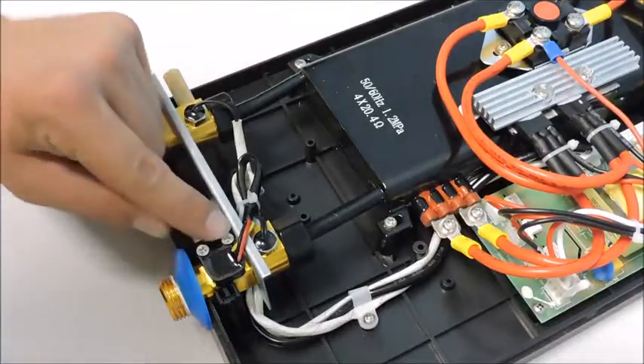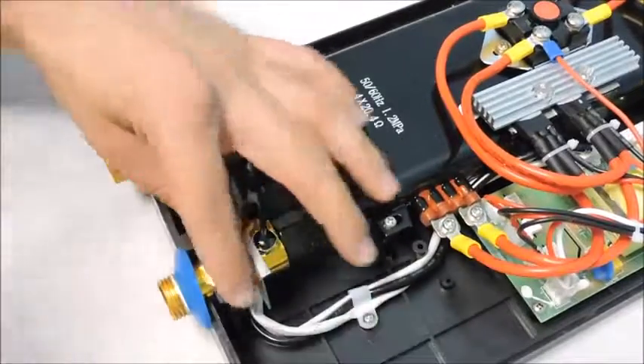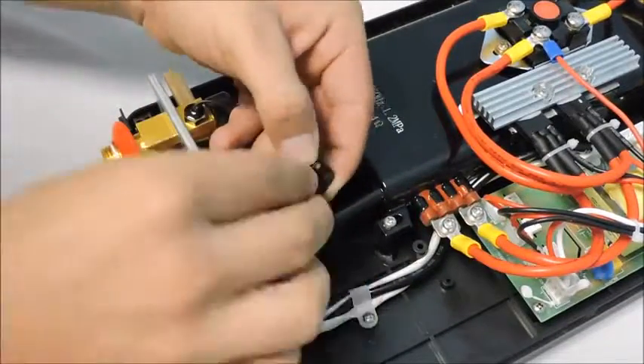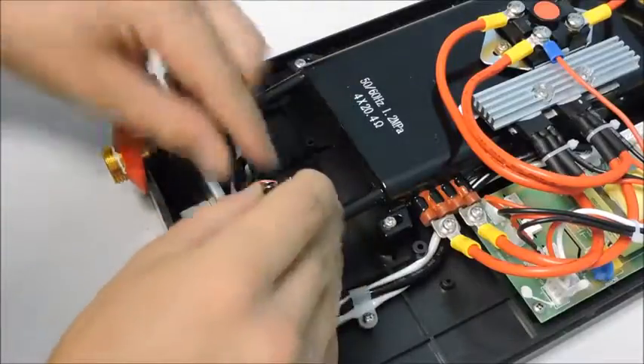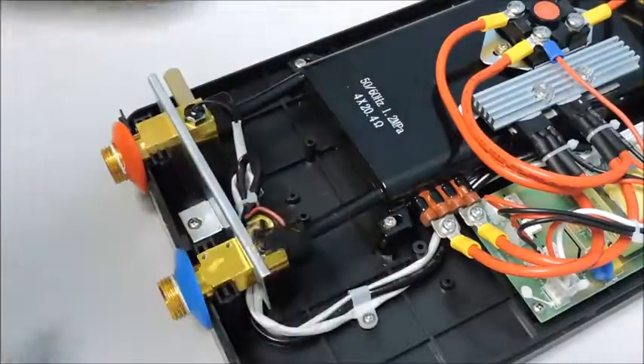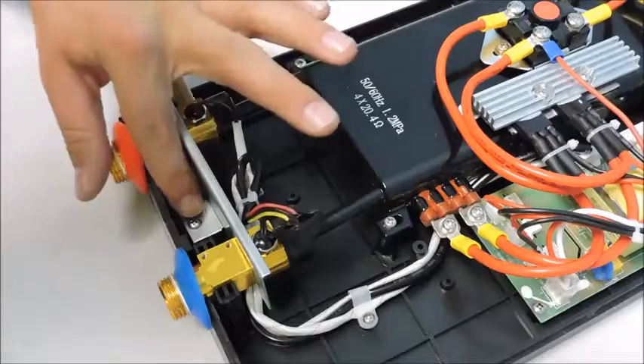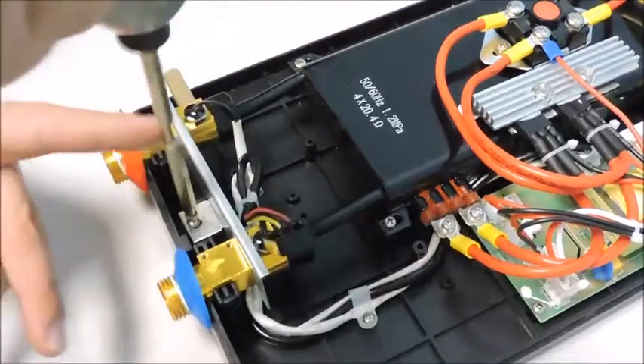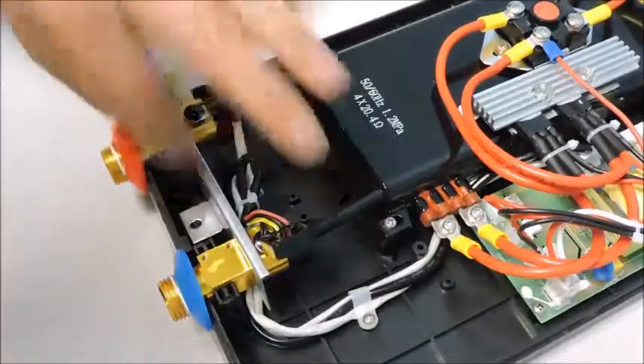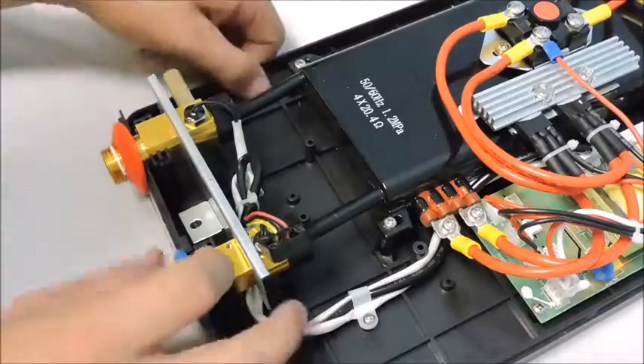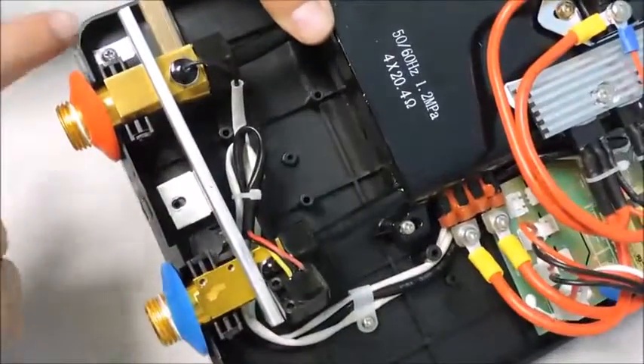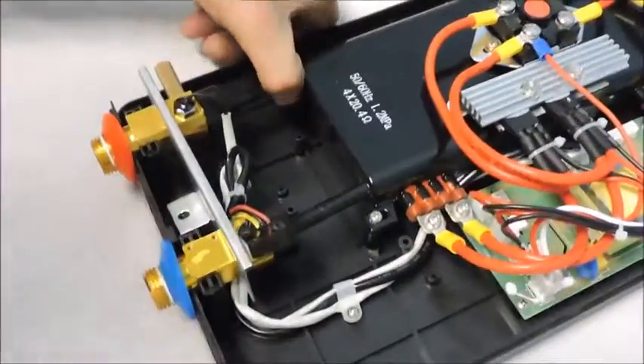Now we will discuss replacing a clogged inlet or malfunctioning flow sensor. Sometimes the impeller sending the information to the PCB will get clogged by sediment or debris and requires replacement. Remove the unit from the wall and place on a flat surface or workbench. Remove the 2 screws securing the black flow sensor on the face of the water inlet. Next, remove the bracket that secures the inlet.